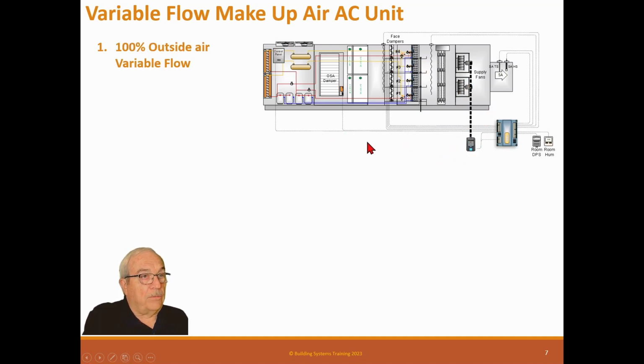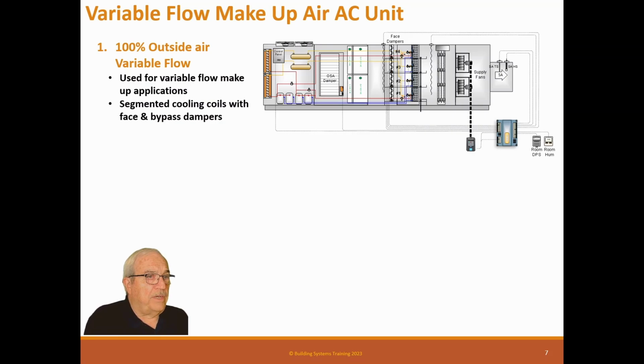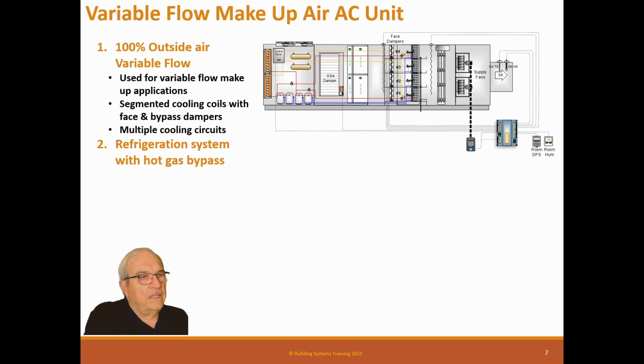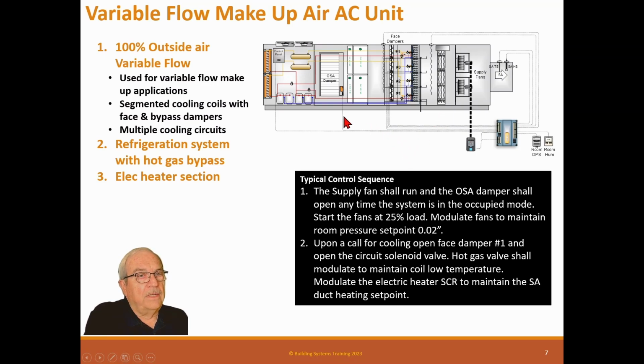It's 100% outside air, variable flow, used for variable flow makeup applications, segmented cooling coils with face and bypass dampers, multiple cooling circuits, refrigeration system with hot gas bypass, electric heater section, probably on an SCR control so we can regulate how much heat we put into there. Here's the sequence. The supply fan shall run and the outside air damper shall open anytime the system is in the occupied mode. Start the fans at 25% load. Modulate fans to maintain room pressure set point of 0.02 inches. Upon a call for cooling, open the fan face damper number 1 and open the circuit solenoid valve. Hot gas valve shall modulate to maintain coil low temperature. Modulate the electric heater SCR to maintain the supply air duct heating set point.